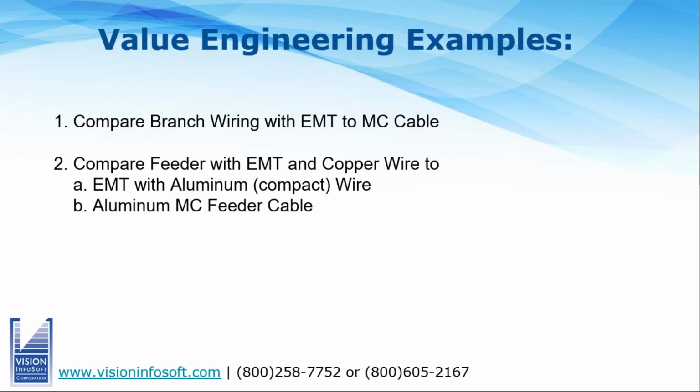And then one I've never done in a webinar is comparing the cost of doing a feeder with, again, the traditional EMT conduit and copper wire, comparing that same feeder with EMT with aluminum wire, what we call compact aluminum wire, and then also doing the same feeder with aluminum MC feeder cable. So we'll kind of take it from one extreme to the other. So we'll get going here.